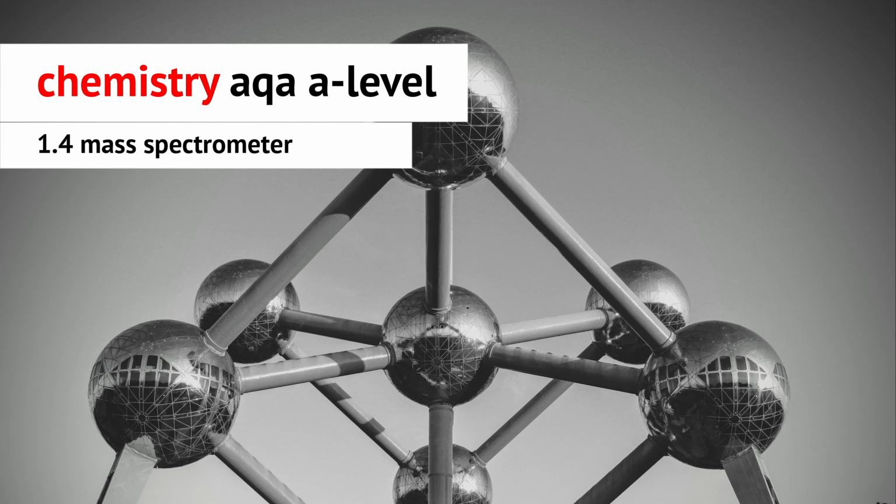Ion drift. The ions pass through a hole in the negatively charged plate, forming a beam, and travel along a tube called the flight tube to a detector. Detection. When ions with the same charge arrive at the detector, the lighter ones arrive first as they have higher velocities. The flight times are recorded. The positive ions pick up an electron from the detector, which causes a current to flow. And finally, data analysis. The signal from the detector is passed to a computer which generates a mass spectrum.